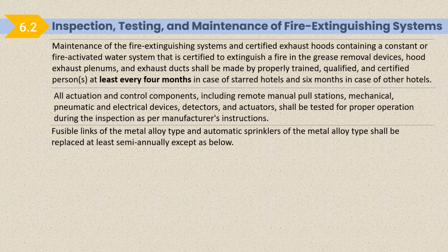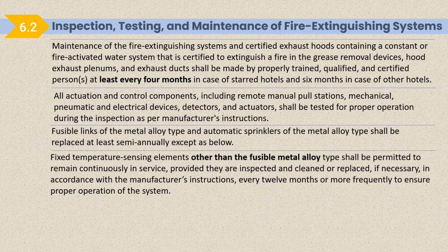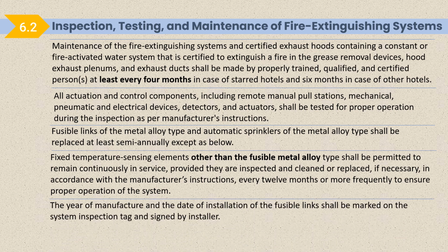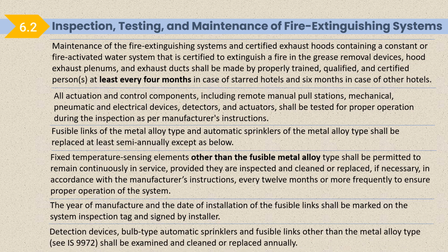Fusible links of the metal alloy type and automatic sprinkler of the metal alloy type shall be replaced at least semi-annually except as below. Fixed temperature sensing elements other than the fusible metal alloy types shall be permitted to remain continuously in service, provided they are inspected and cleaned or replaced if necessary in accordance with the manufacturer's instructions every 12 months or more frequently to ensure proper operation of the system. The year of manufacture and the date of installation of fusible links shall be marked on the system inspection tag and signed by the installer. Detection device, bulb type automatic sprinkler and fusible links other than the metal alloy type: you can take the reference of Indian Standard 9972, which says the sprinkler head for fire protection service shall be examined and cleaned or replaced annually.